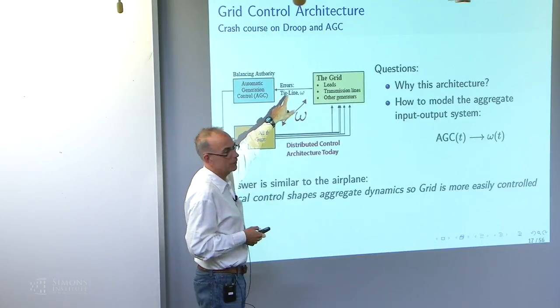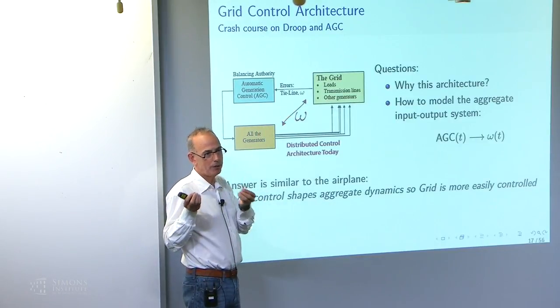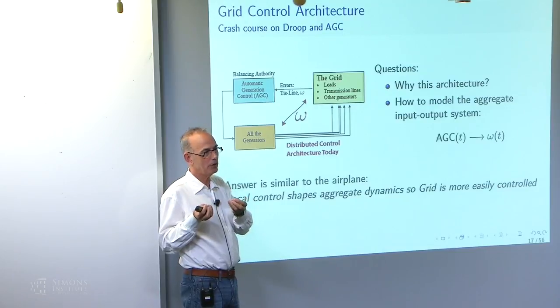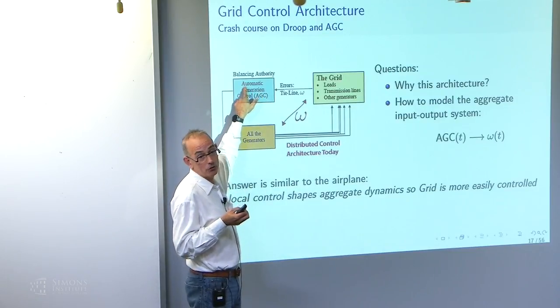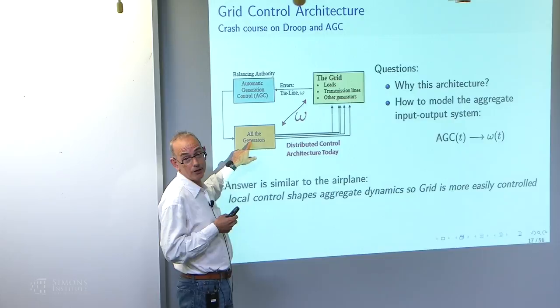All right, so this is what it looks like. They measure these tie-line errors between balancing authorities, and they measure frequency deviation. They put it through a PI controller, and it goes out to all the generators, with different scalings for different generators.